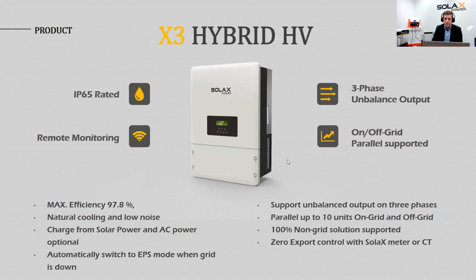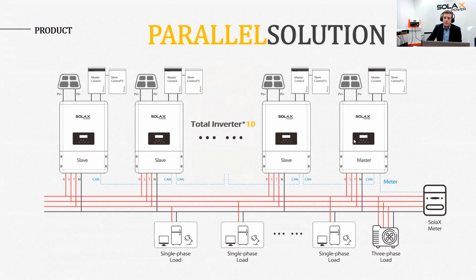Okay, let's go on. This picture shows two things: the clusters in master-slave mode, and the balanced and unbalanced mode. The inverter on the right is the master, connected via CAN to the slave, and you can build a system with up to 10 inverters. You always go from CAN 2 to CAN 1 - the master has the CAN 2 interface, going to the CAN 1 interface on the second inverter. I can show you this on the X1 hybrid inverter since the interfaces are the same.